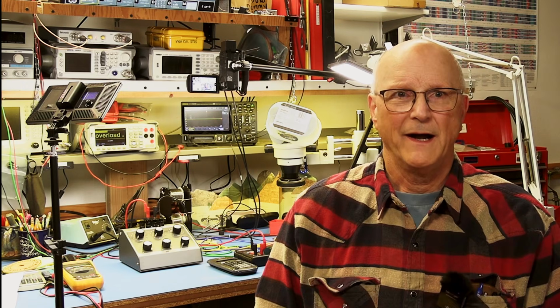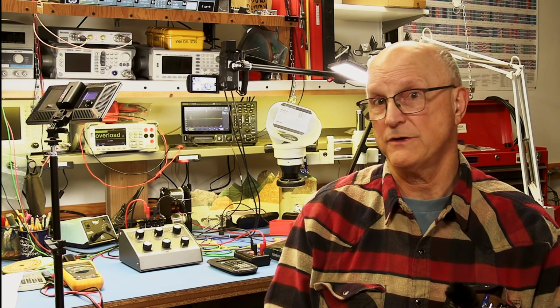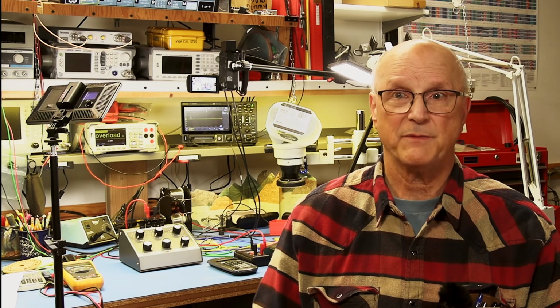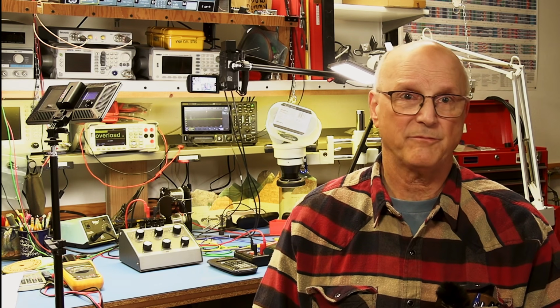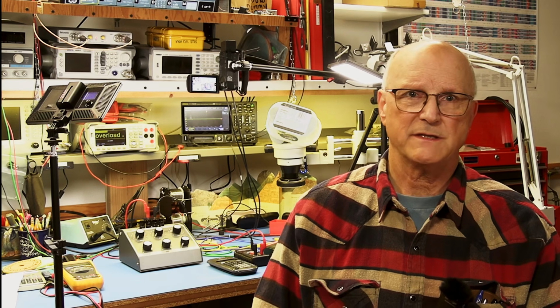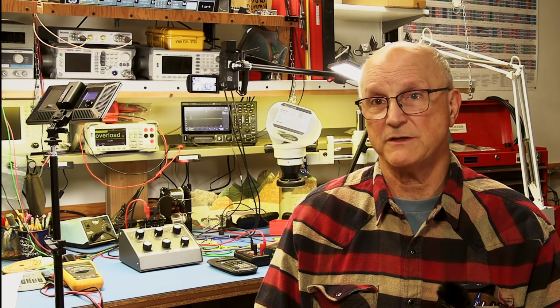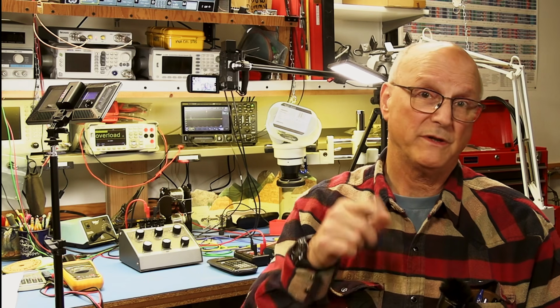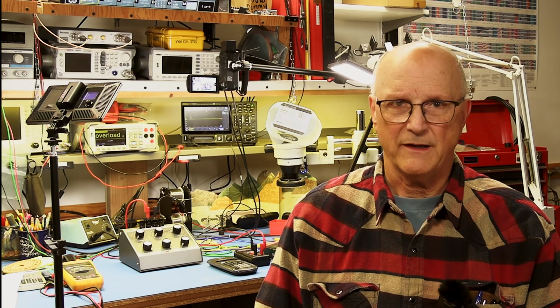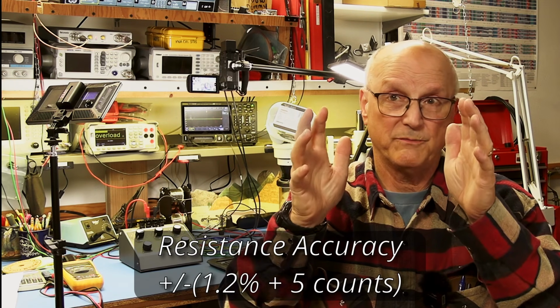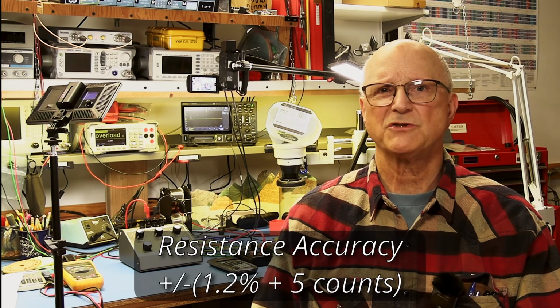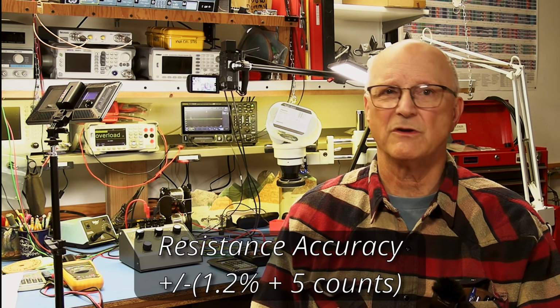Well, the last thing I'm going to take a look at will be the actual accuracy of the meter. I'm just going to quickly go through a few measurements and see how it stacks up. I have not done a full-on calibration of the meter. I did do a spot check at a few select points. The AC and DC voltage measurements look very good based on the checks that I made. I'm very pleased with those. On the other hand, the resistance measurements, which are supposed to be within plus or minus 1.2% plus 5 counts, came in just a little way out of tolerance on the low side.